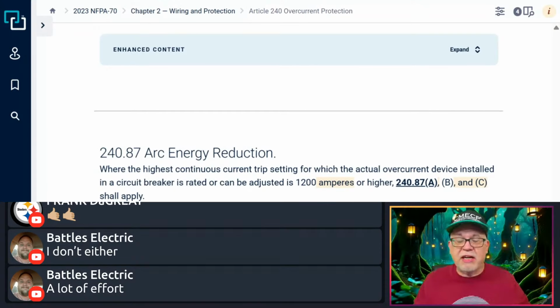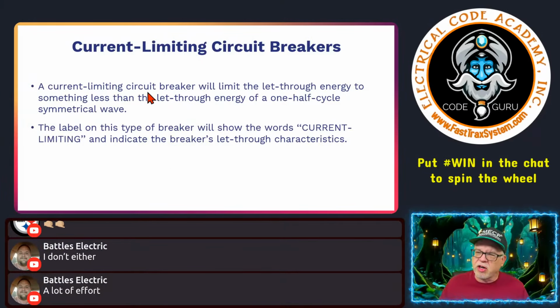Okay, all right, current limiting circuit breakers. A current limiting circuit breaker will limit the let-through energy to something less than the let-through energy of a 1/2 cycle symmetrical wave. The label on this type of breaker will show the words current limiting to indicate the breaker's let-through characteristics. So if you have an application that calls for a current limiting circuit breaker, similar to current limiting fuses, it's only going to let a certain amount of current through in a certain half cycle.